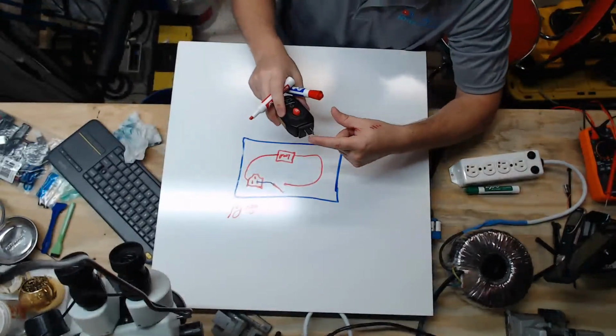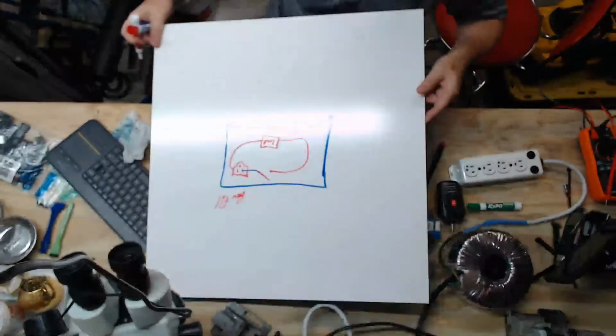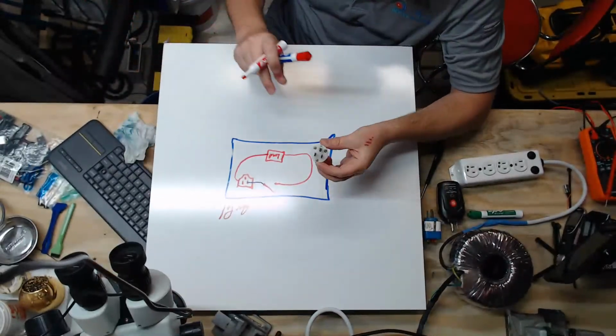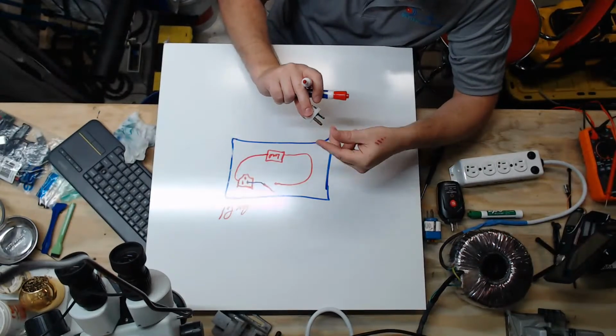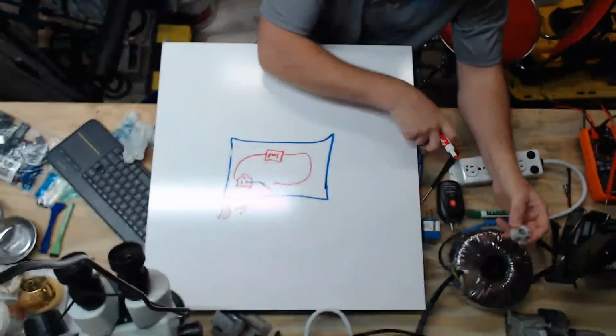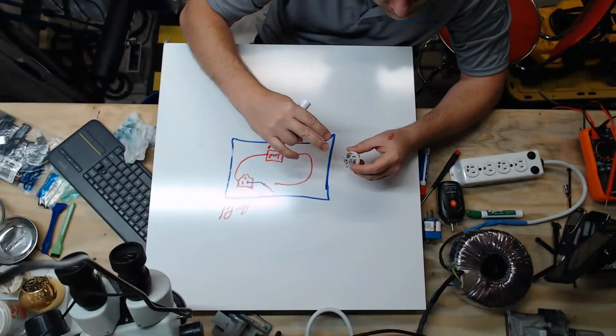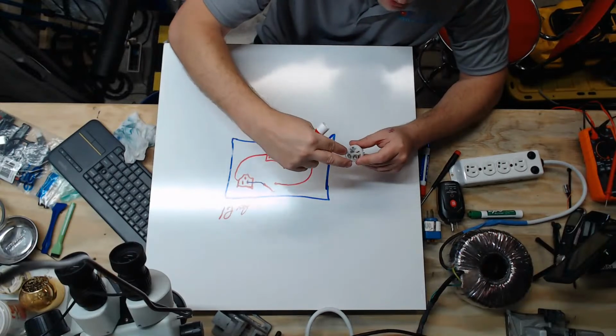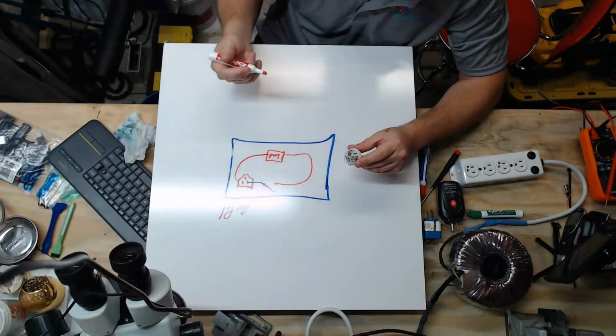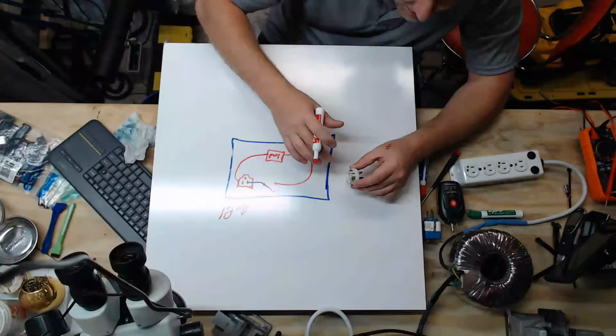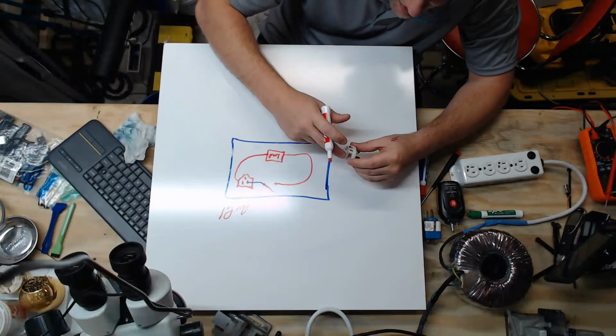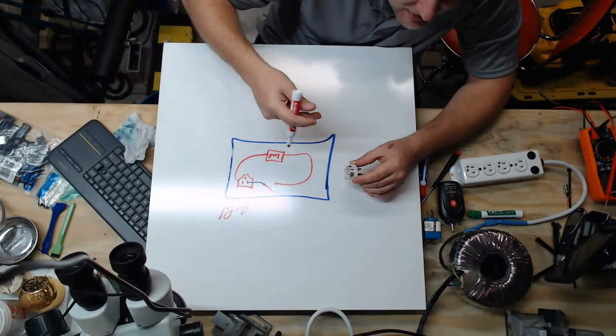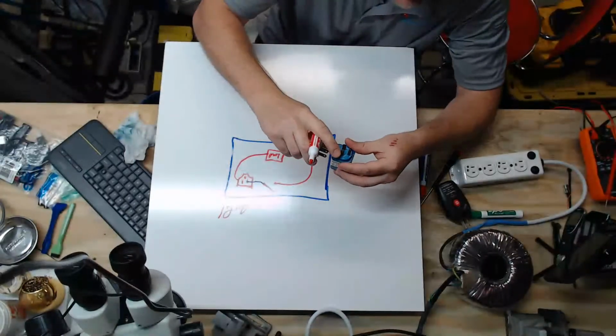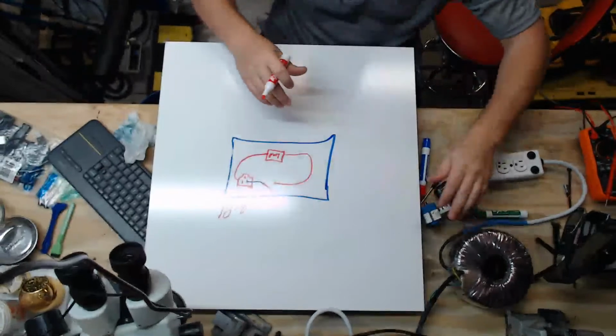And what I mean by that is that you take this wire and this wire in your electrical cord when you wire it, like this guy right here, and you reverse those two wires. Or on the inside of your device, when you have your spade connectors that connect to the back of your IEC outlet, you reverse them when you reattach them. Whenever you detach electrical wires on the inside of your medical device, try and take a photo if you don't remember which side is line and which side is neutral. Because if you reverse them on the inside of your medical device, then all these other safety features that are all the way back to the power pole, there are so many safety features that are built into electrical code.